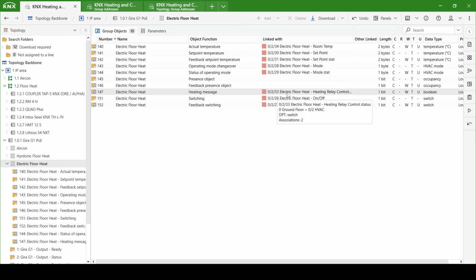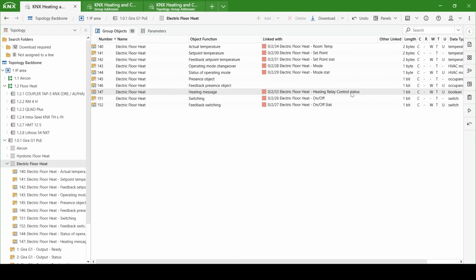This is the heating relay control status. If I open this up a bit, you'll see here. And that's actually telling the Gira visualization whether there is heating currently at the moment or not. So you might have the set point set and the thermostat turned on. Is the actual floor heating up, or is the floor cooling down, or is it heating up or cooling down? And that comes off the status from the relay.